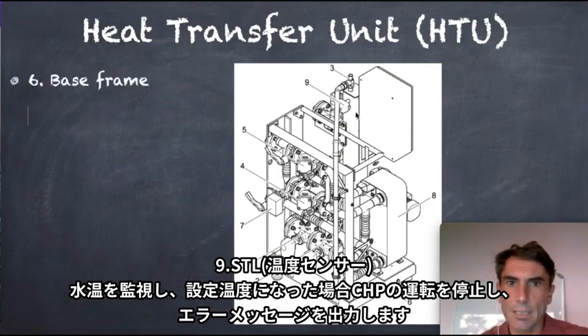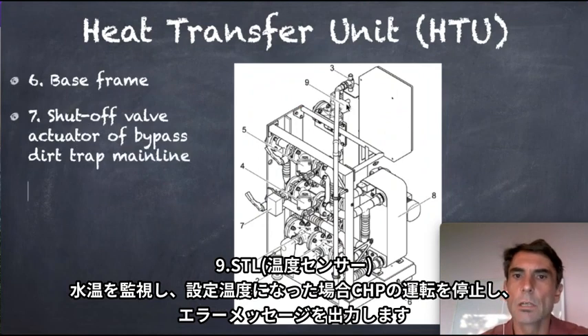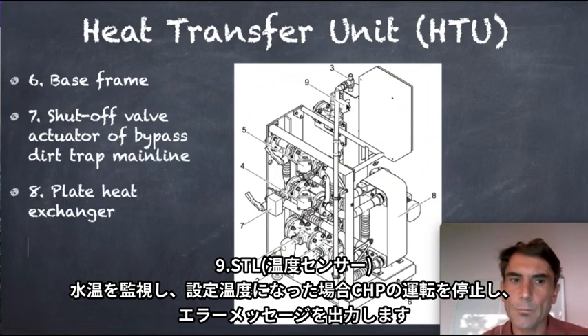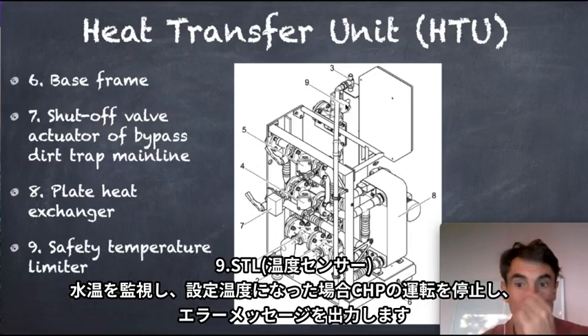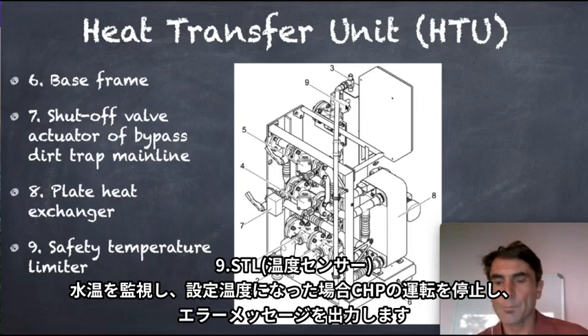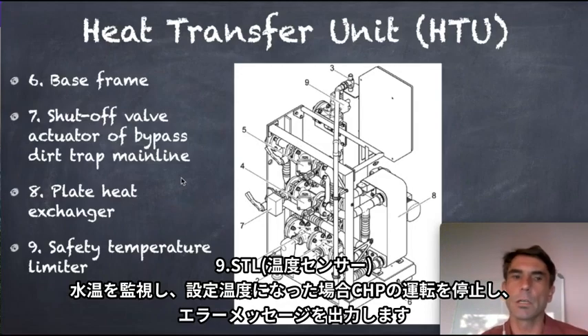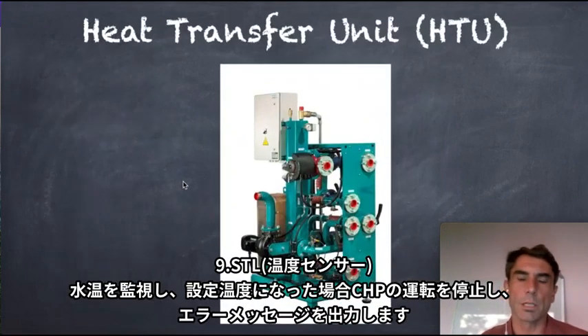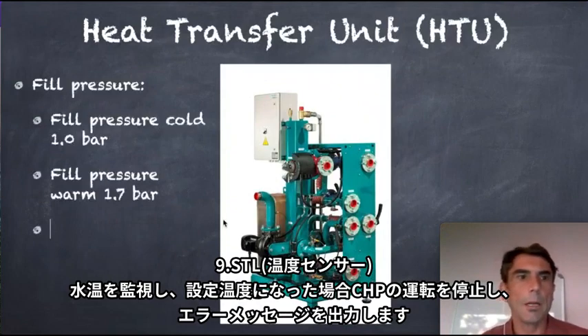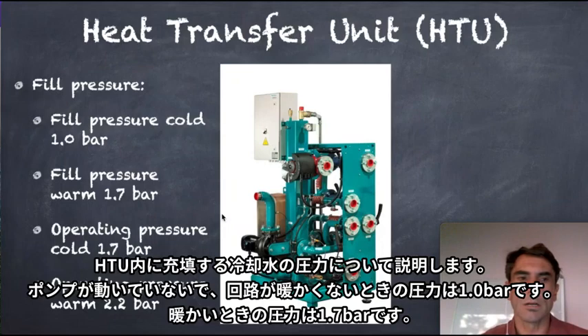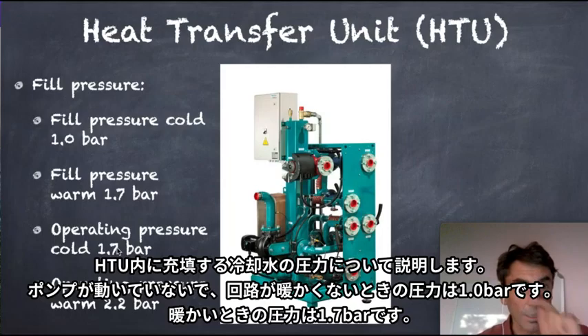Oh, I forgot number 9. Number 9 is here the over temperature switch, or limiter. It's on top, a gray box, to measure the temperature. This is a switch, which means if we exceed the temperature, it will switch off the CHP with an error message. Okay, so filling pressure, heat transfer unit. The filling pressure when cold is 1.0 bar. The warm filling pressure is 1.7. So if we operate warm, that means the pumps are operating, the pressure should be at 1.7 bar.